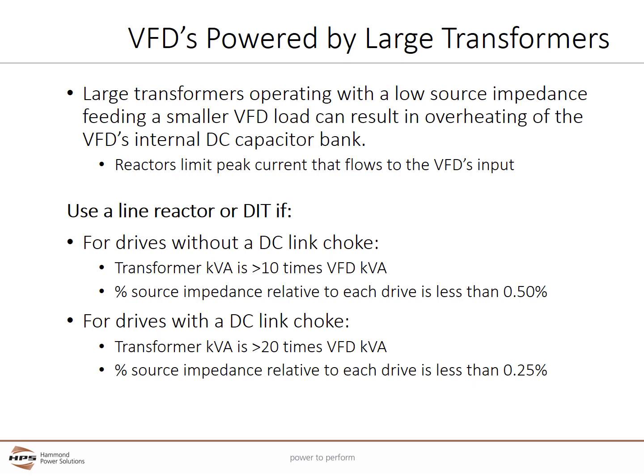This is an issue that not a lot of people are aware of. It is common that a VFD is powered by a transformer which is significantly larger than the VFD's individual load. A large transformer appears as a low impedance source to the VFD, which can cause overheating of the internal DC capacitor bank. As a rule of thumb, use a line reactor or DIT if the VFD doesn't have a DC link choke and the transformer supplying the drive has at least 10 times the current capacity of the VFD. If the VFD has a DC link choke, consider adding a line reactor or a DIT if the transformer's kVA or current rating is greater than 20 times the VFD's current rating.